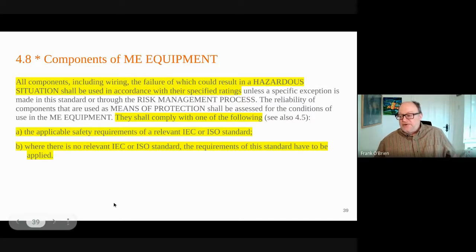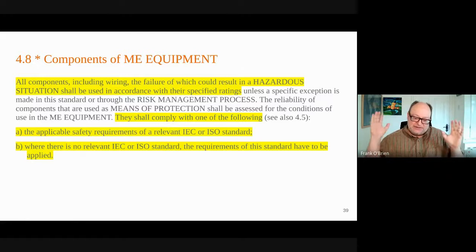All right, so 4.8 is that clause in the beginning, the general clause that talks at a high level about what's required. After it talks about having risk management, identifying essential performance, an expected service life and an alternative risk control measure, and 4.6 for touch protection, 4.7 is single fault safe.